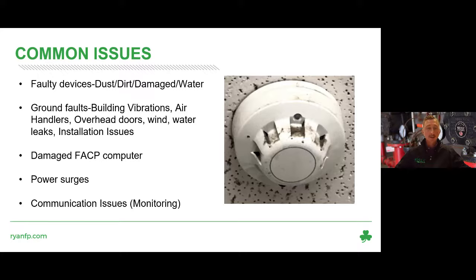We all know that. Ground faults are another very difficult, very common thing that we see. They can be difficult to track down, but simply put, your fire alarm system is constantly monitoring your wiring as well, and a lot of people don't know that. So when the metal in the building vibrates or touches the fire alarm wiring, this can create a ground fault.